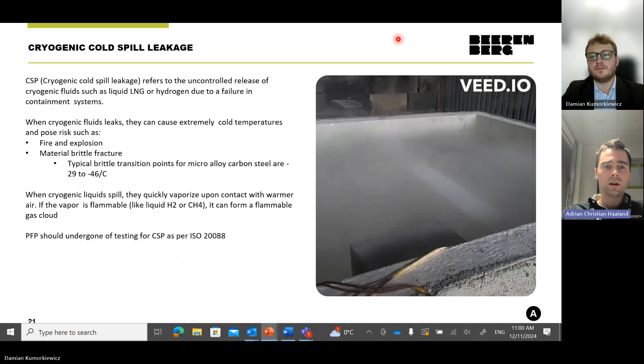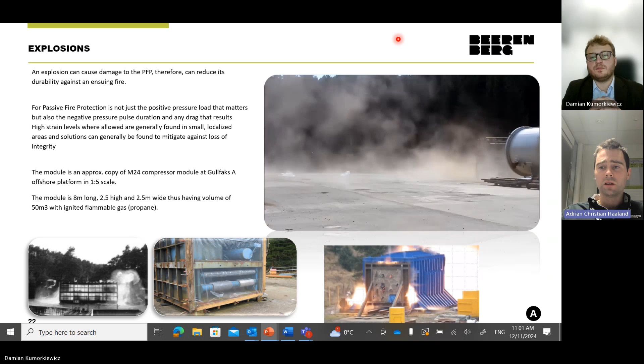Here is a brief snapshot of an explosion test. This was an open module to capture the effects of drag forces as well. You will see on the video soon to be shown here that we have test specimens fixed on the end of the container module, which you also see a picture of in the bottom center picture here. The intent of this type of testing is to verify that the product can actually retain integrity when being subjected to quite extreme explosion pressures generated from igniting gas sources in the process area. Typical pressures from this can range from 0.2, 0.3 up to 1.5 bar for a typical gas explosion scenario.